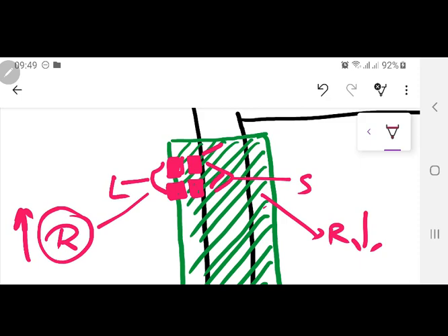And this is very problematic, because it's already very difficult to cool down the core. The ones which are very far away are already cooled down because oil is also touching them. They are already in contact with oil over there and they already have a low current. So this is a very big problem: how you are going to manage these four conductors, or maybe six, or whatever that may be. How you are going to make the resistance of each one of them the same.